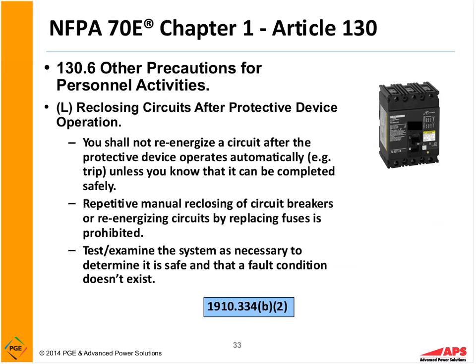Okay, so when we look at other protective equipment and precautions for personnel activities, we should be wearing proper protective equipment, let's say if we're opening up gear. We have what's called personal protective equipment for shock and arc flash hazards. But one of the things that we don't want to do is create the hazard to begin with. One of the things I see violated a lot is if you have a circuit breaker or a fusible disconnect, like a switch with fuses in it, if the fuse blows or the breaker trips, you are not to reset that unless you know it can be done safely. Now, if you had an overload, like a motor was jammed up and we've cleared the overload and we know the overload caused the breaker to trip or the fuses to blow, yes, we can reset it if we know we can do it safely.